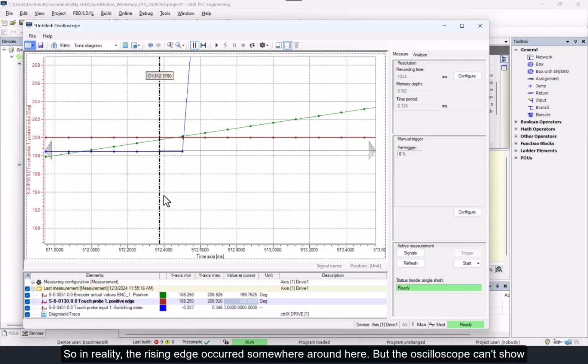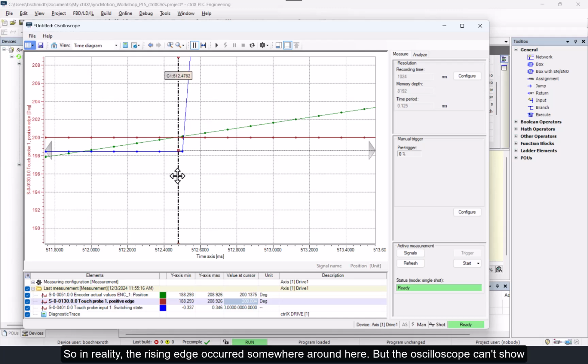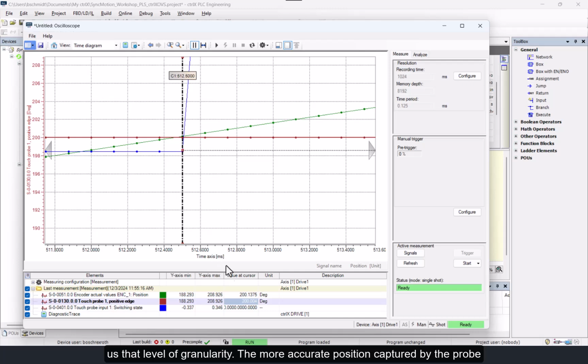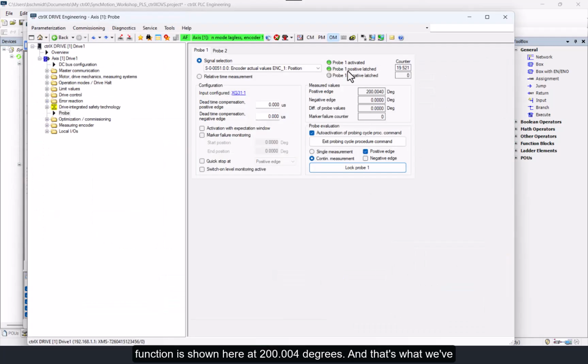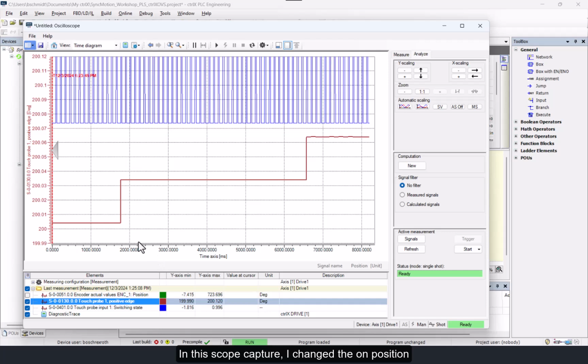So in reality, the rising edge occurred somewhere around here, but the oscilloscope can't show us that level of granularity. The more accurate position captured by the probe function is shown here at 200.004 degrees. And that's what we've been looking at here. In this scope capture, I changed the on position twice in increments of 0.03 degrees. And we can see it reflected in the captured position.